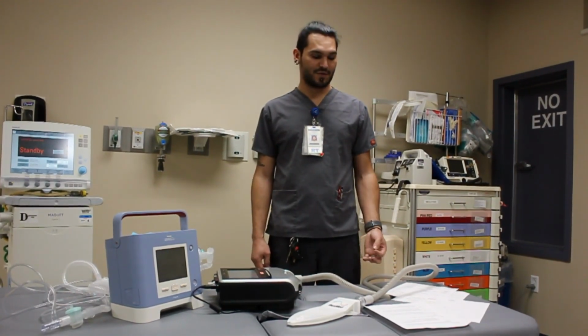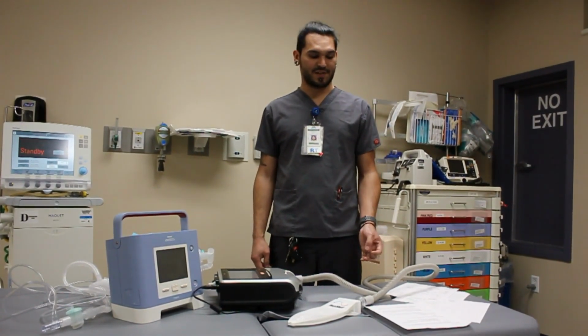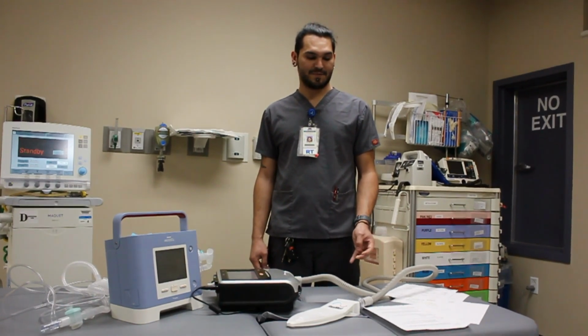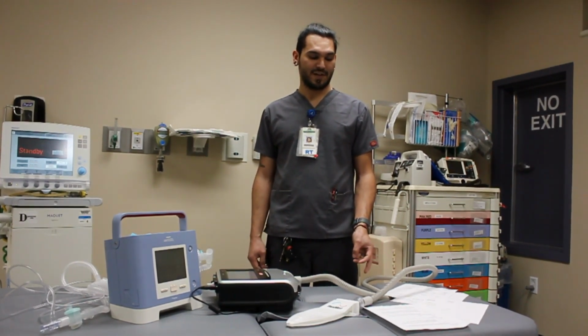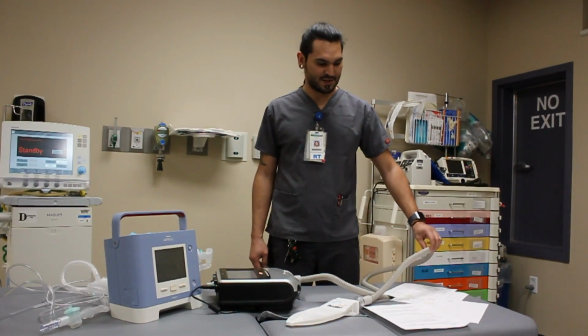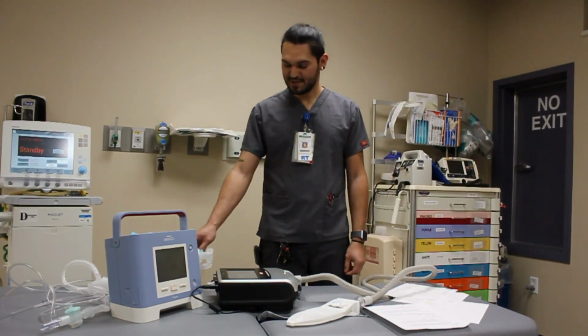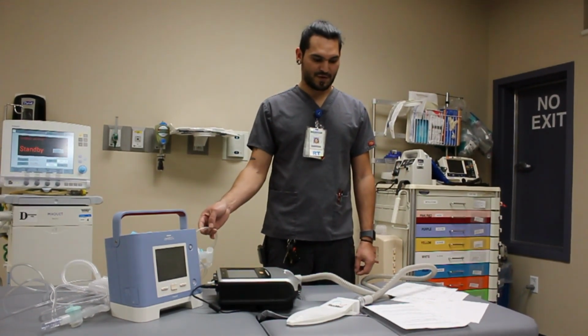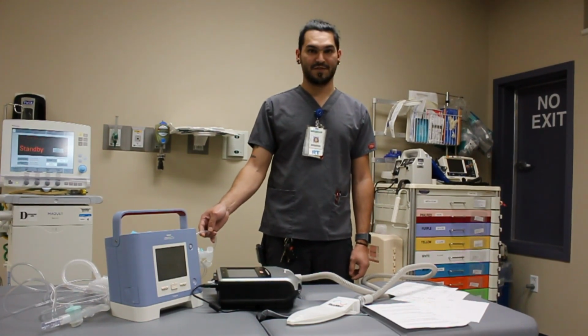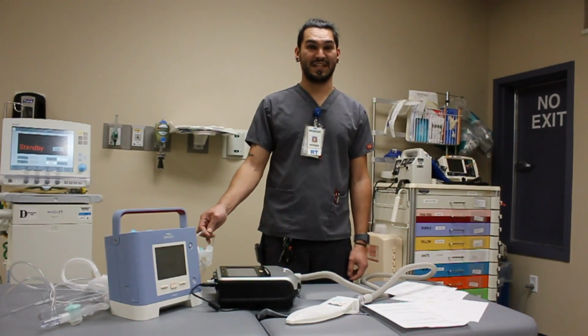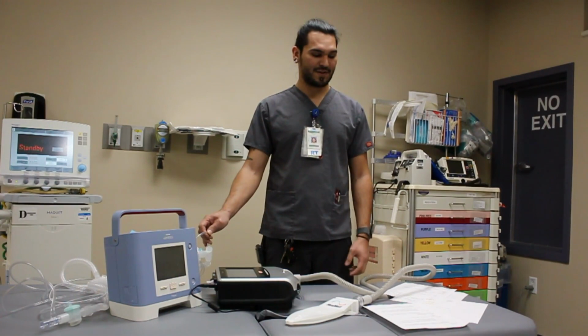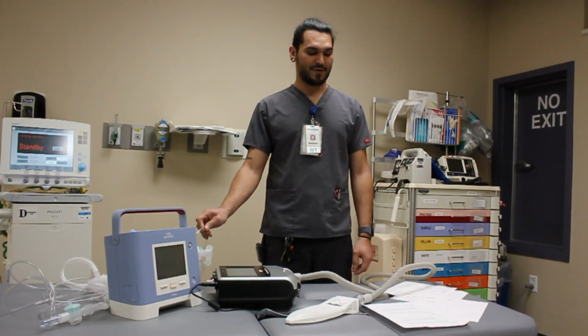First off, we're going to look for coughing, increased secretions, bronchospasm. Is there anything obstructing the airway? Water sloshing inside the tubing? Blocked pressure lines? Or possibly a partially occluded ventilator circuit? If it isn't cruddy, something on the end of it, just any reason that it would cause the pressure to go up, we would troubleshoot that.